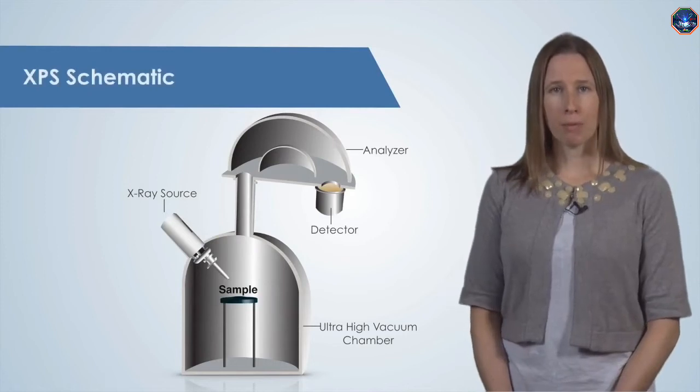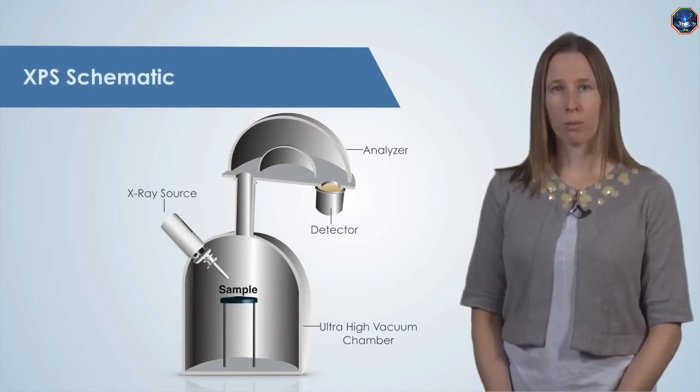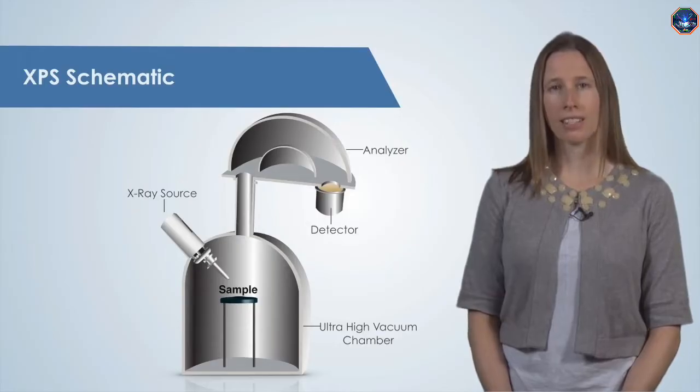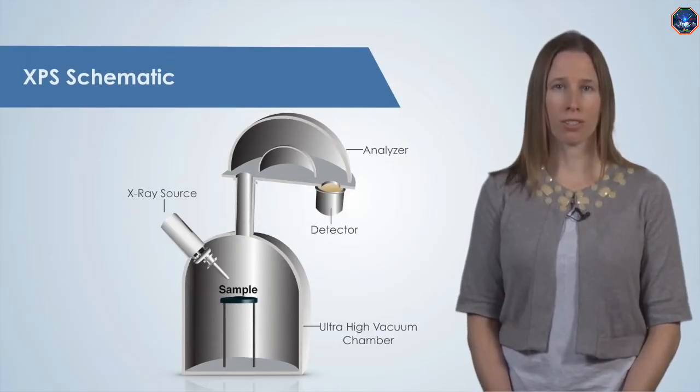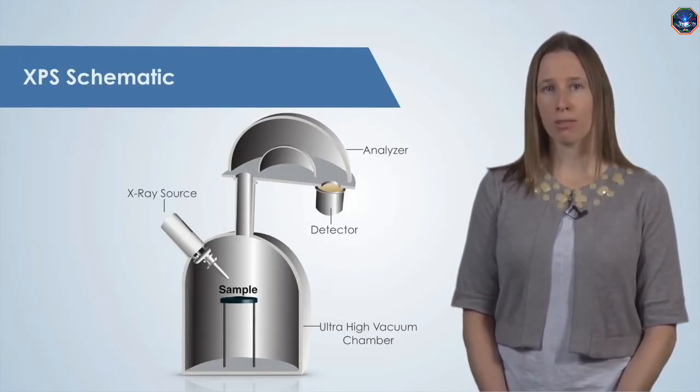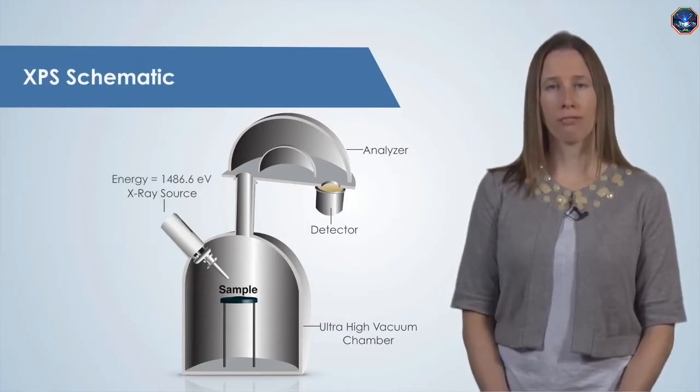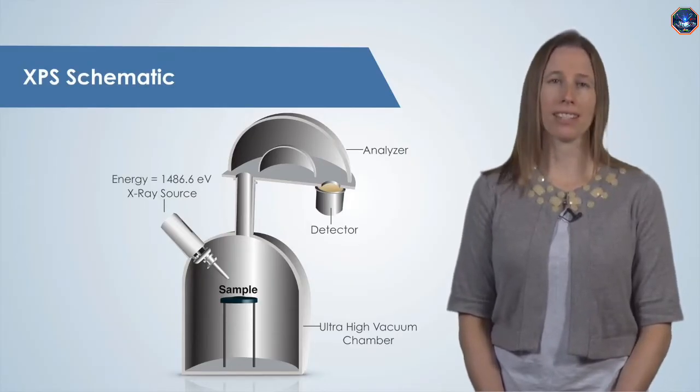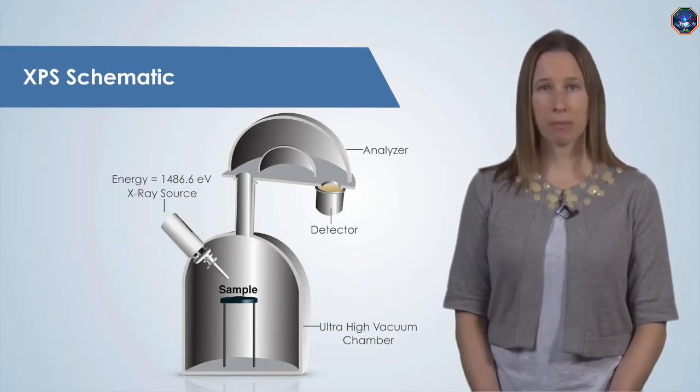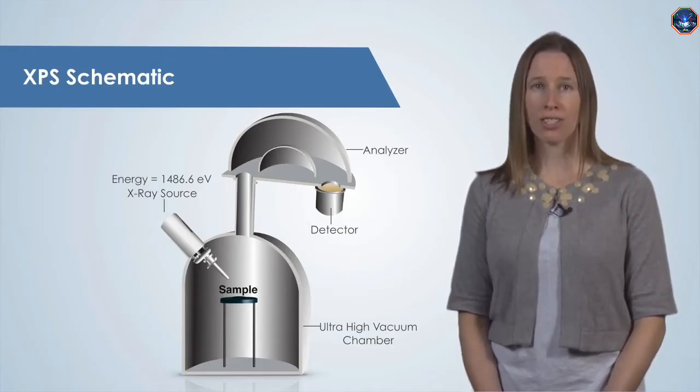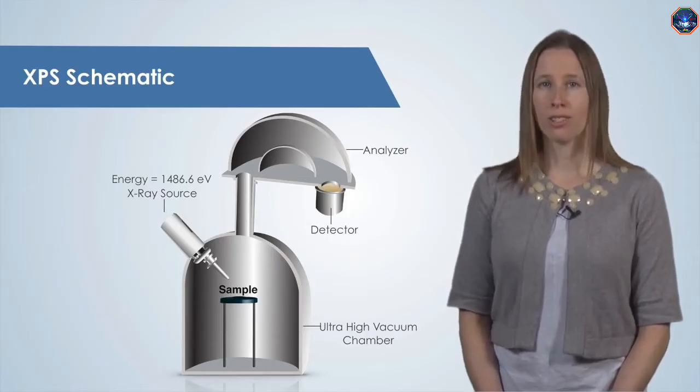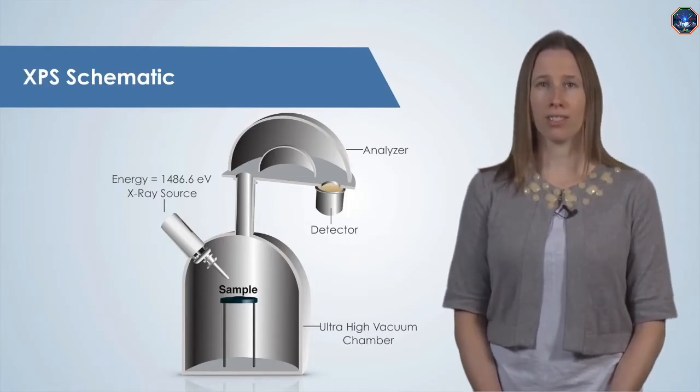The XPS experiment takes place in an ultra-high vacuum chamber, where pressures are typically in the 10 to the minus 9 torr range. One of the most common X-ray sources used in XPS has an energy of 1486.6 eV. As a comparison, visible light has energies of only 1.5 to 3 eV, so these X-rays have a lot of energy.